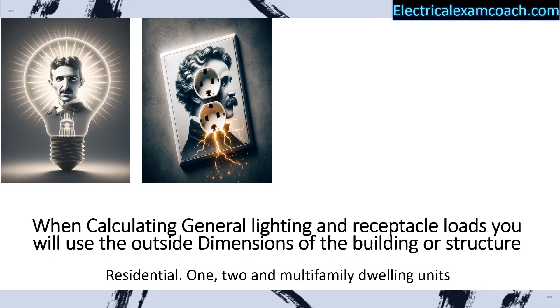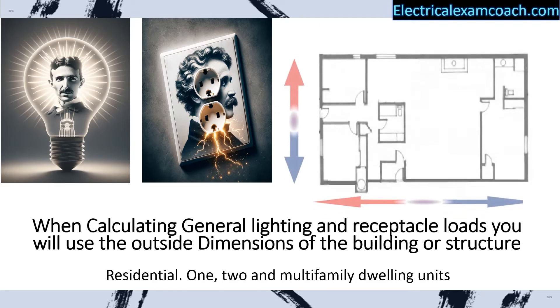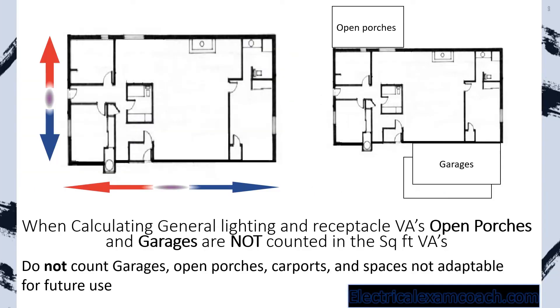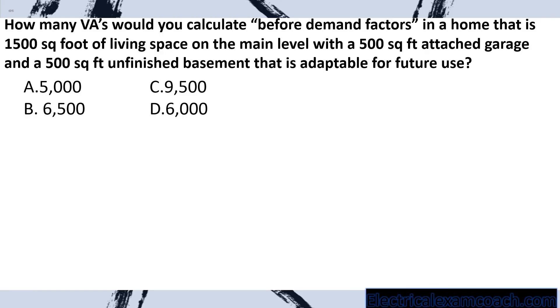When calculating our general lighting and receptacle loads, we will use the outside dimensions of a building or structure — we measure from the outside of the building in both directions to determine square footage. Open porches and garages are not counted in our general square foot VAs. We do not count garages, open porches, carports, and spaces that are not adaptable for future use. Now — how many VAs would you calculate before demand factors? I haven't taught you what a demand factor is yet, so I'm going to teach you a little bit at a time, and by the time we round back around to it, you'll be a pro at it.